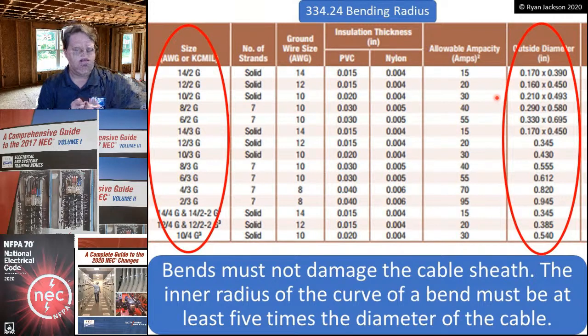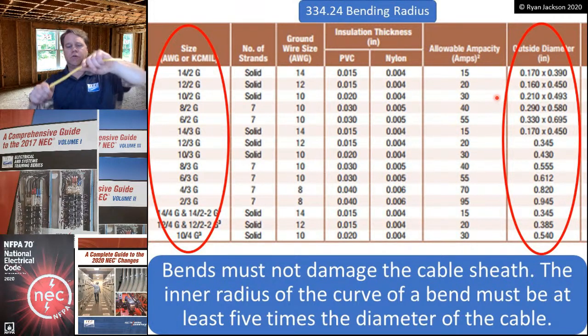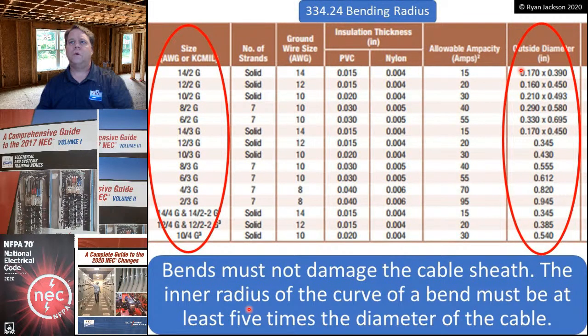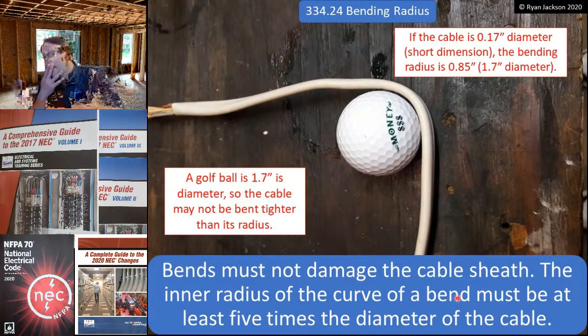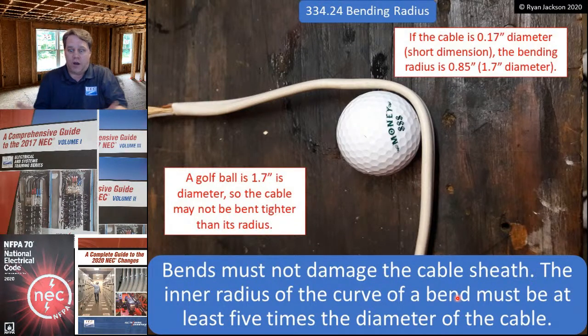So if I'm bending it the normal way that we would bend it, then it's the thickness this way that I'm concerned with, and that's the smaller dimension. So I thought, okay, what is 0.17 times 5, the diameter of the cable? What does that even mean? I do the math, and it's 1.7, and I'm like, okay, I have no idea what that means. I know what 1.7 inches is, but I need something else. I can't understand this. So I thought, okay, what else is 1.7 diameter? A golf ball. I looked online, there's got to be something, and it's a golf ball.